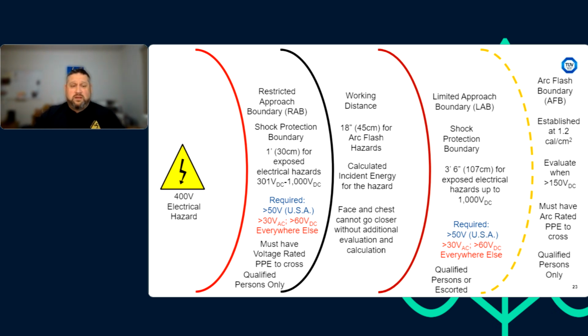I was just working with a company the other day that is manufacturing batteries, and they don't have protection built into their system at the level that they're having workers work with these modules. And they found out that they have a significantly high, I'll just say in the ballpark of 18 calories, that they are exposing their workers to, and they don't have PPE for that currently. So this is why we don't want to just assume that category 2, which is rated for 8 calories, will protect us, because in that particular example, they far exceeded category 2 and they didn't even know it.